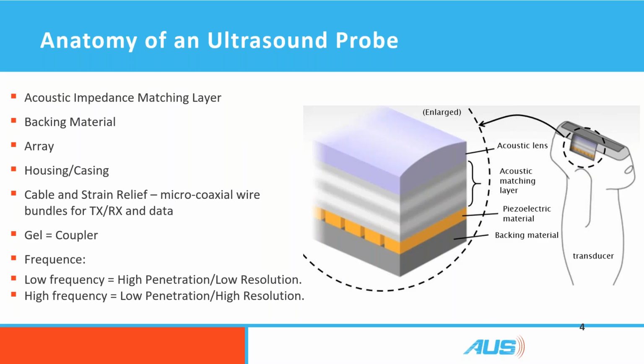Again, during the preventative maintenance, make sure you take your time and inspect the cable thoroughly and look for damage to it, so we can prevent further damage. This can cause image artifacts if the cabling inside is damaged. So do a good inspection on this as well.